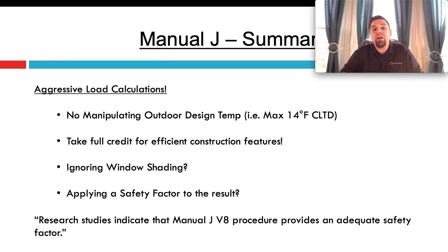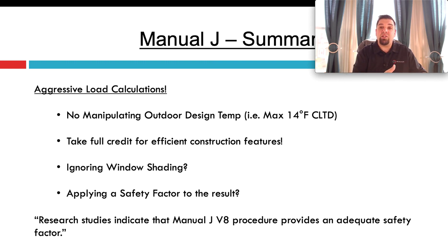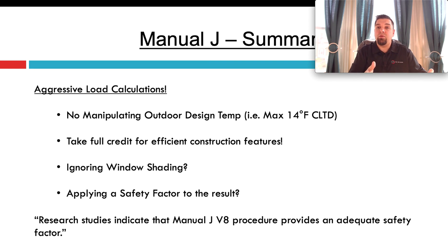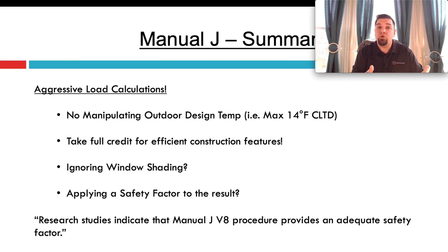Do not manipulate the outdoor design temperatures. In Massachusetts, I know that if I hit a 14-degree delta T between my design temperature inside and outside in cooling, I know I've gone too far. That's a very simple, quick, easy check to see what the temperature difference is for cooling load. Anything past that is outside of design — we're designing above our 99% design temperatures.